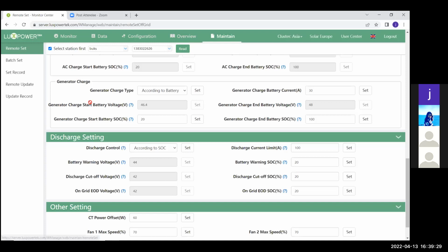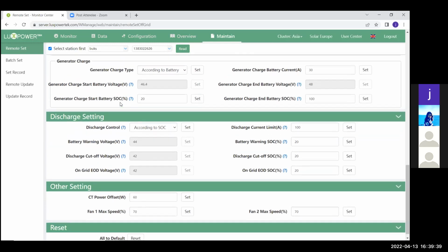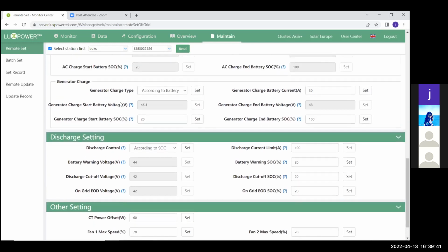So generator charge works the same as AC charge. You can set it according to battery voltage or SOC, and from there on you can go. Just remember, after every setting that you change, you must press the set button. If you don't press the set button, the setting won't save on this inverter and won't reflect on your side if you read all your settings again.